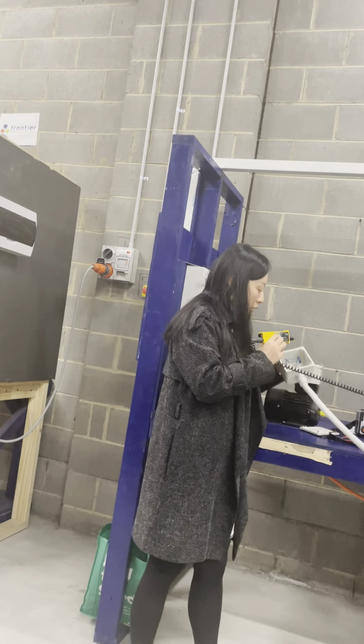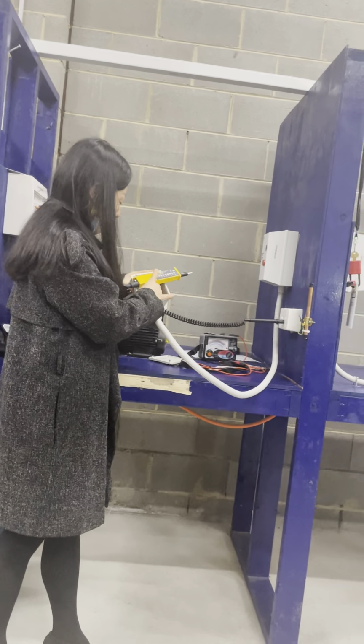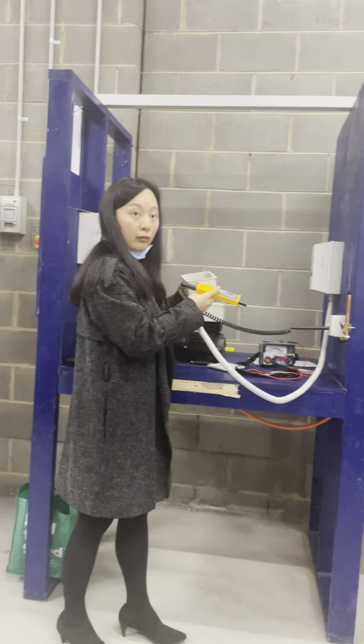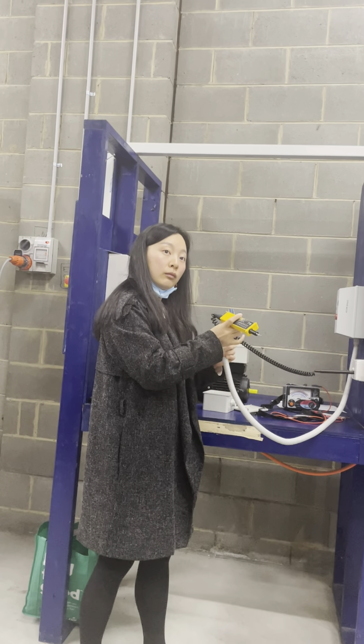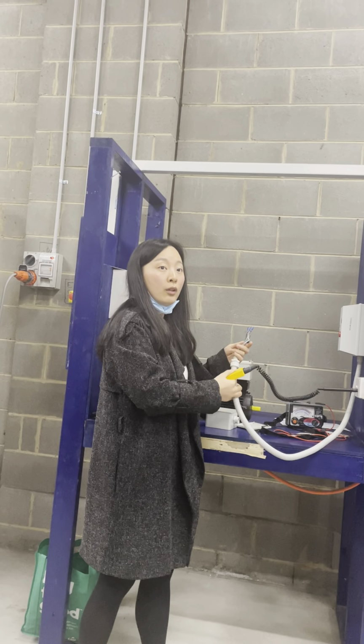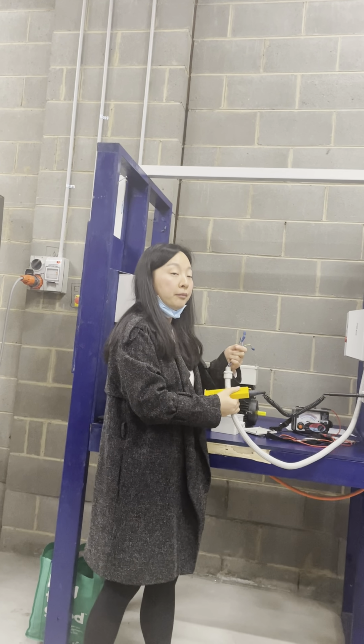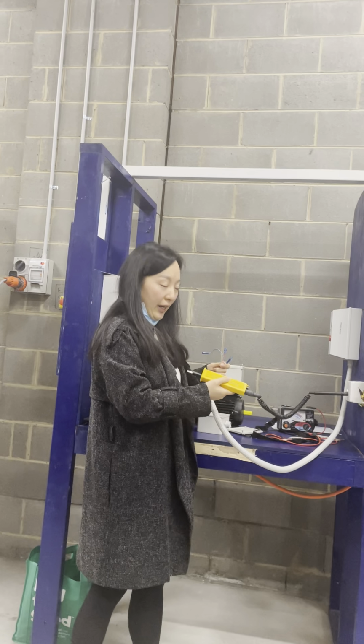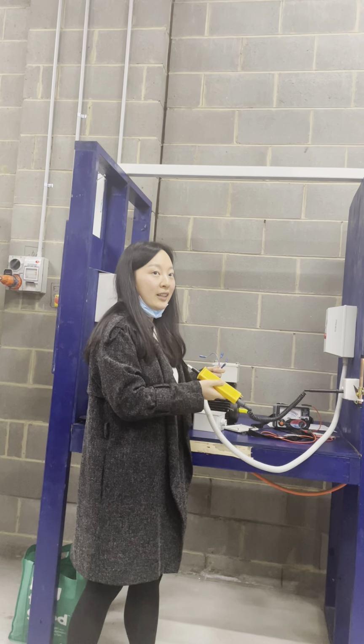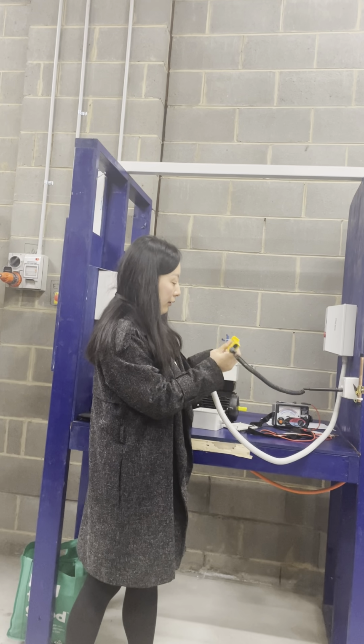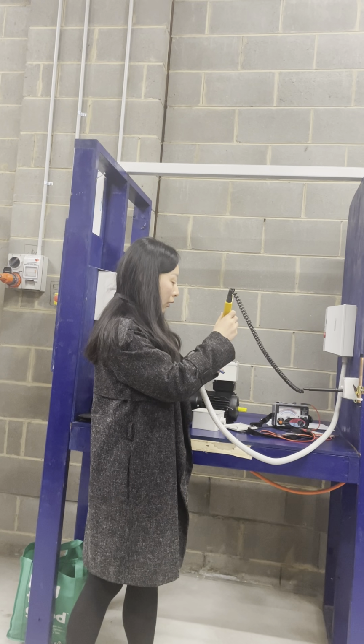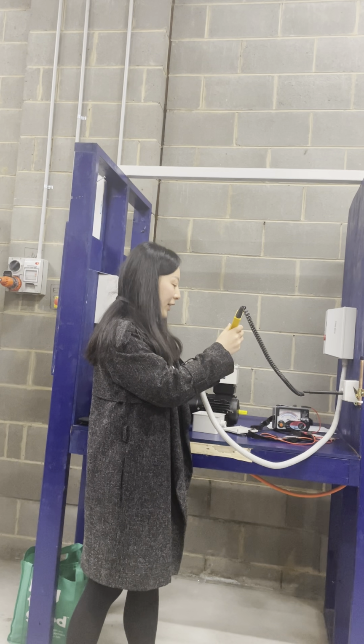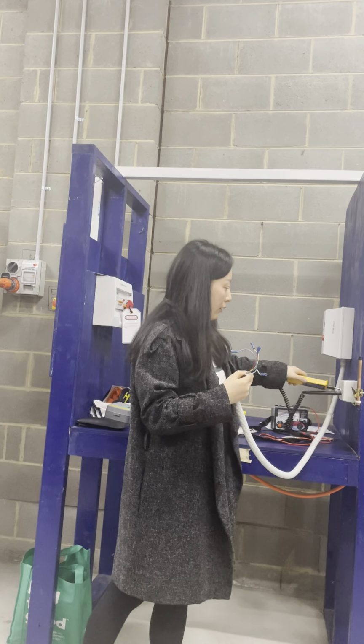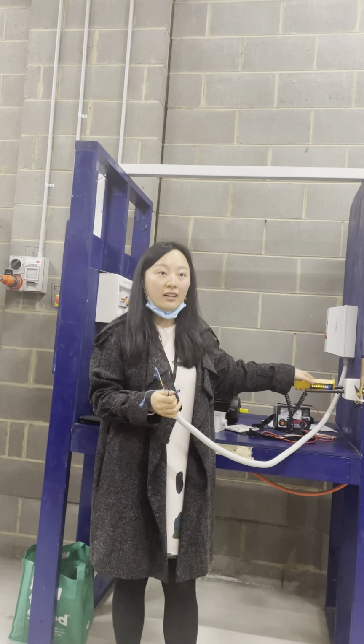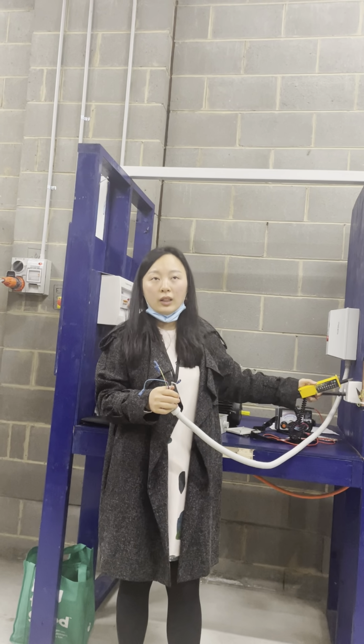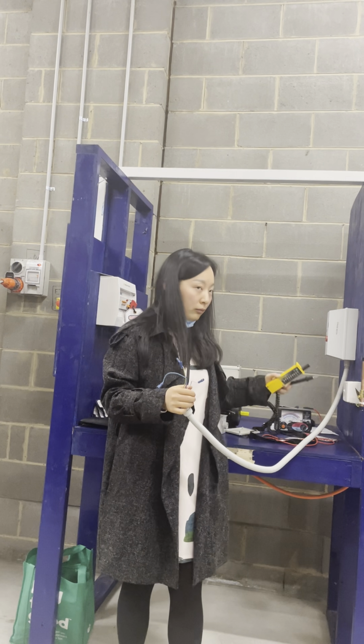Between each individual one, so phase 1. With this part, are you allowed to touch the terminals? Yes, of course, with your gloves on. You have to, otherwise how are you going to hold them? It's really hard to put a tester in there without holding it. Correct, yes. So phase 1, nothing. Phase 2, earth. Phase 4, phase 3, nothing, okay? Now retest your tester. Do you have to say that when you're doing it to the tester? Phase correct, 1, phase 2, phase 3.